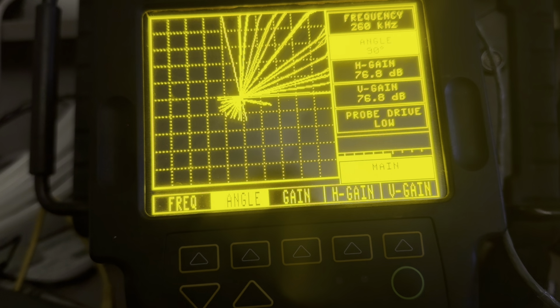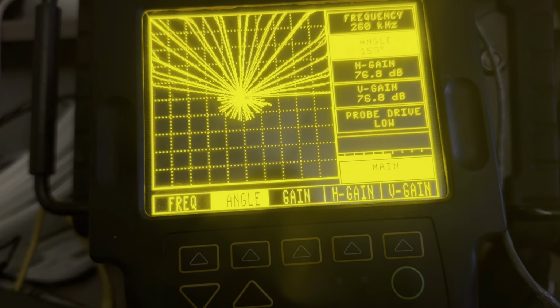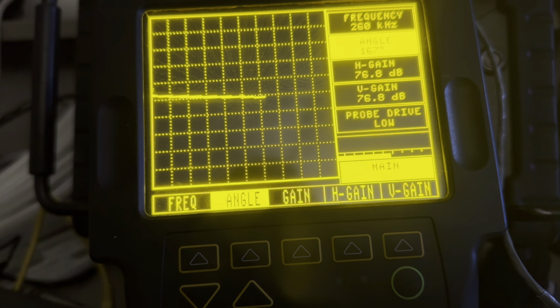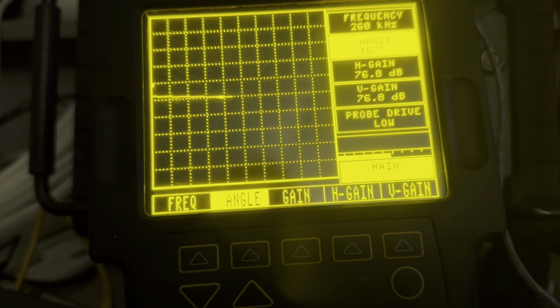No problem. We just rotate that phase trajectory around to get probe motion horizontal, or as the technical folks like to call it, the magnetic field coupling efficiency, liftoff, fill factor. But since we're doing surface, we're talking about liftoff, and that's the distance between the coil and the material. So I hit erase and I lift off. The impedance point goes off screen because the coil right now, I'm holding it in air, which means it's unloaded. There's no material to load the coil.